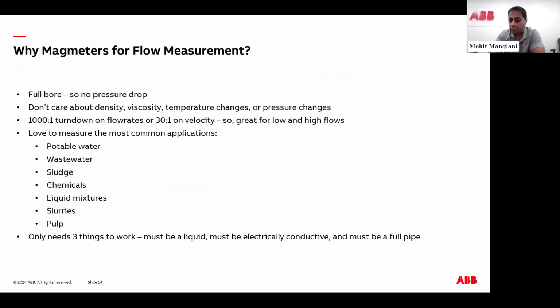So why mag meters for flow measurement? You saw what the operating principle is. Obviously, it's a flow meter. It's an accurate device. The big kicker on mag meters is that it's a full bore device. There are a lot of flow meters out there, and there's no one perfect one for every application, unfortunately. Mag meters are full bore, so there's no pressure drop. In technologies like Vortex, Swirl, Coriolis, Venturis, anything in line, you're going to have a pressure drop. You're paying for pressure, relying on gravity to give you pressure inside that line, and obviously you don't want the device to absorb all of it. So a mag meter is nice because it's a full bore device.